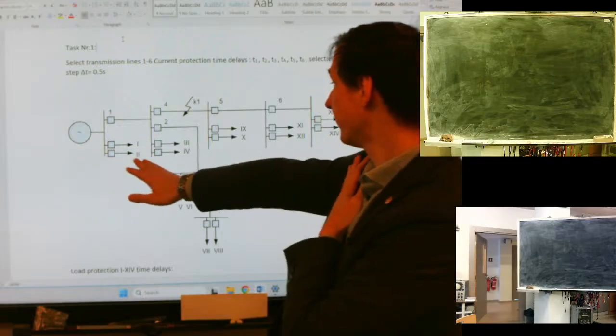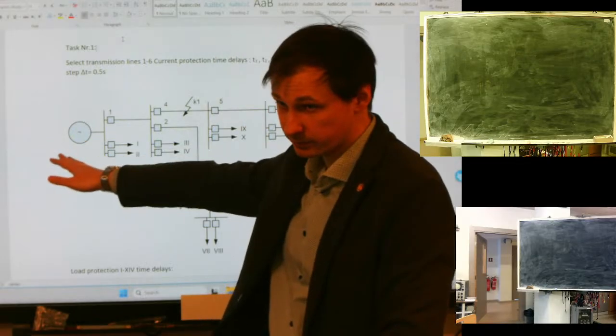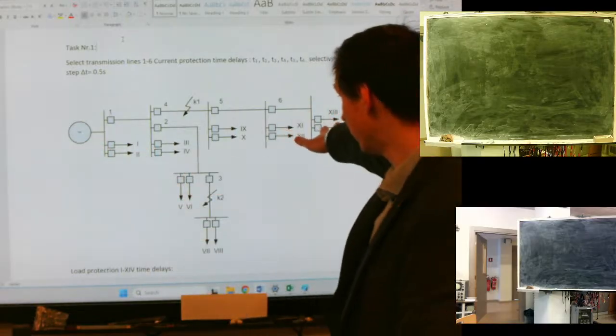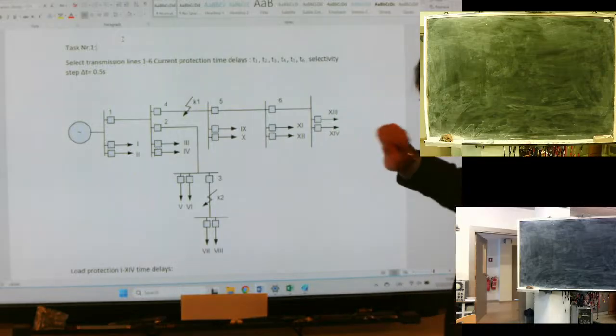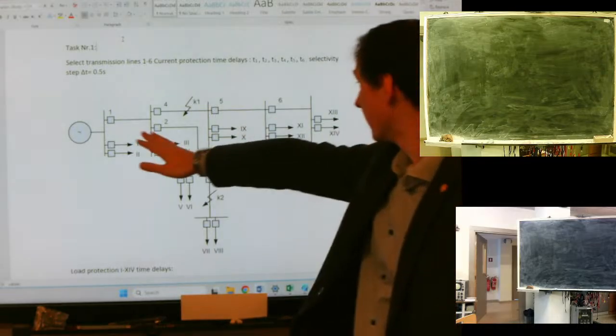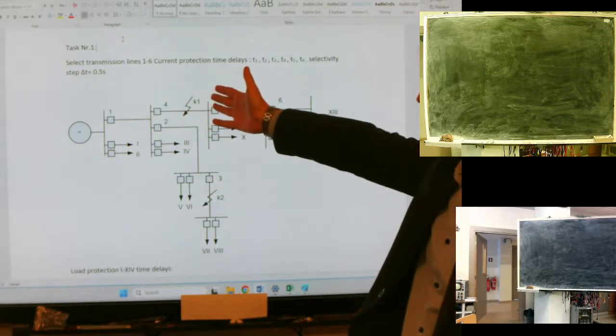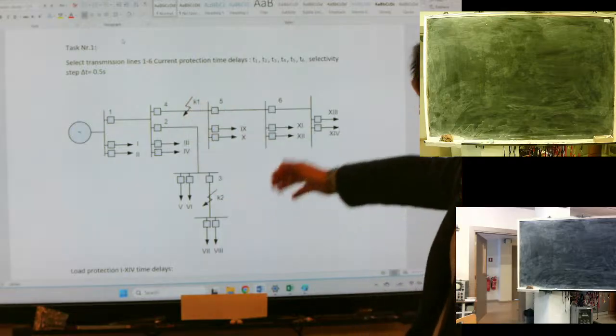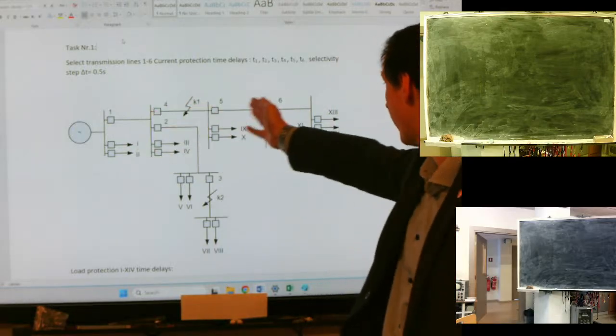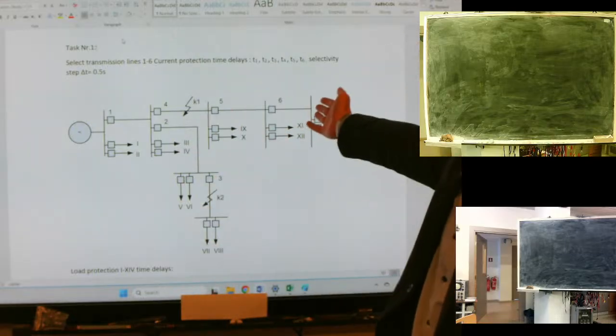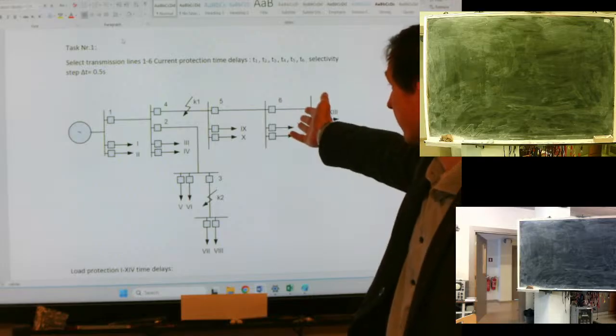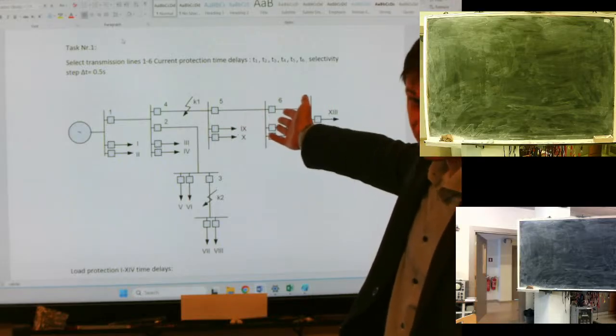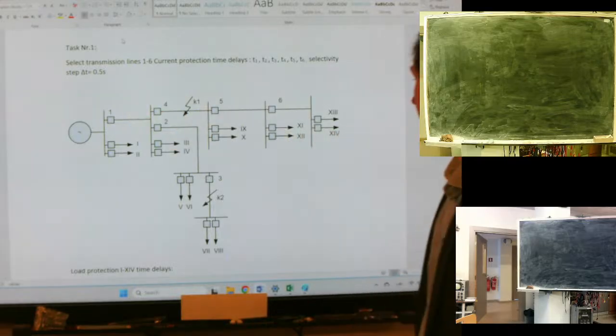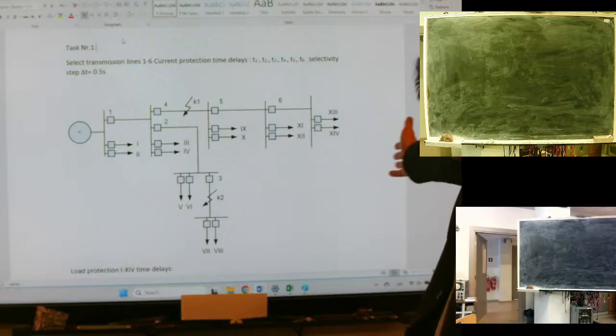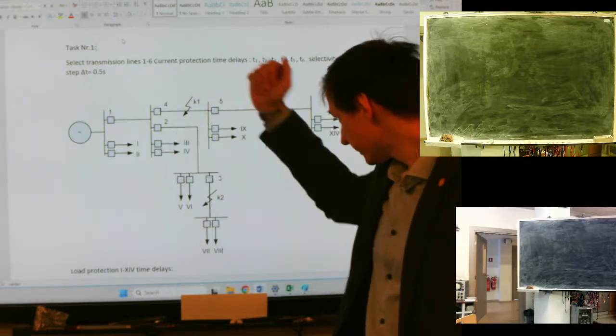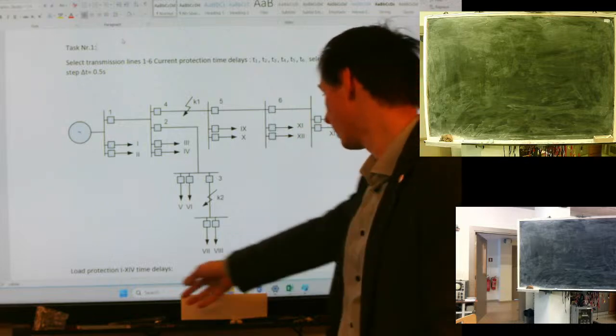From the left, let it be from the left, is a source of power, concentrated, and we have radial lines in series. Every line has its own protection. So here we have numbers 1, 4, 5, 6, 2. Total number of lines is 6. And the current protection is the same. We have 6 current protections, one for every line. And we have multiple loads, with Roman letters, from 1 to 14.